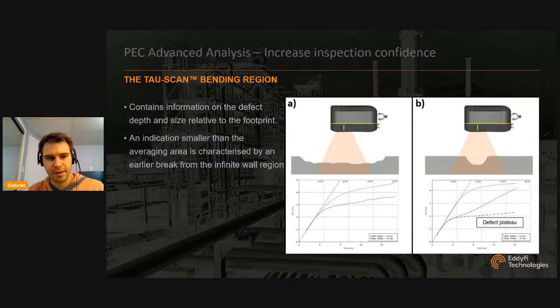The bending region of the Tau scan, the middle part, contains information on the defect depth as well as its size. If you've got a smaller indication like this one here, you'll see the signal curve in black leave the calibration curve earlier on. That's because in that Tau scan, there is information from two different wall thicknesses. You get a plateau region that's defined by the defect, which is the characteristic decay time of the defect. And then you've got another plateau that comes up later, which corresponds to the surrounding nominal wall thickness. Whereas if you're scanning an area of generalized wall loss larger than the probe averaging area, the bending point is going to be later in time. So the curve is going to leave later and end with just one plateau.